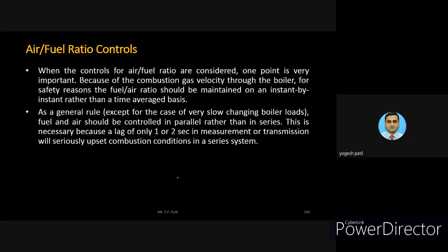As a general rule, except for the case of very slow changing boiler loads, fuel and air should be controlled in parallel rather than in series.